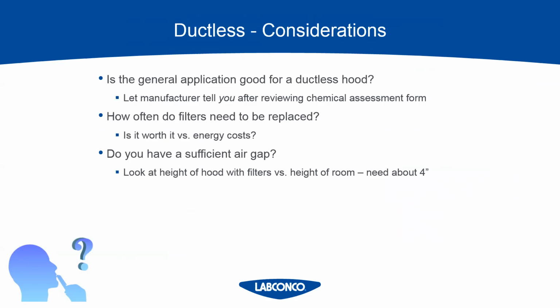This includes any type of accessory HEPA filters that people sometimes have on these hoods for nuisance particulates. You'd have to be 4 inches above that HEPA filter. So if you need to double check, call a manufacturer, have someone double check, because if you don't have this air gap, the hood is actually not going to work effectively at all. It would be like having no hood. Do you rent or own the space? This is probably an obvious one, but if you don't own the space, maybe you can't put a hole in your rooftop, and then obviously you would be looking at ductless hoods.